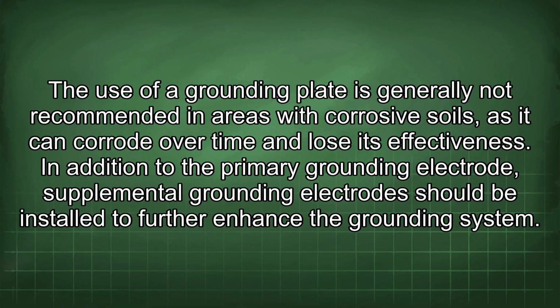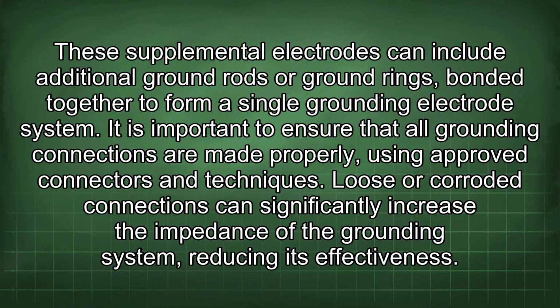In addition to the primary grounding electrode, supplemental grounding electrodes should be installed to further enhance the grounding system. These supplemental electrodes can include additional ground rods or ground rings bonded together to form a single grounding electrode system. It is important to ensure that all grounding connections are made properly using approved connectors and techniques.